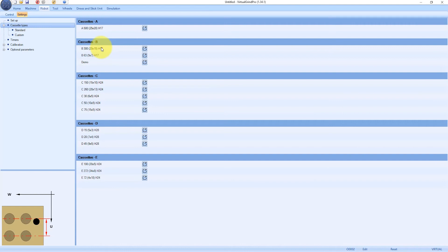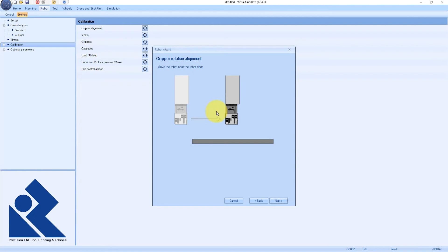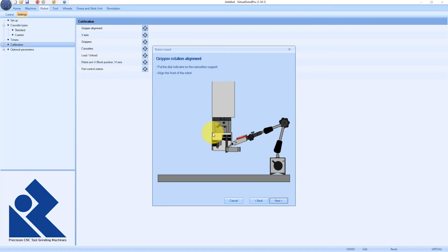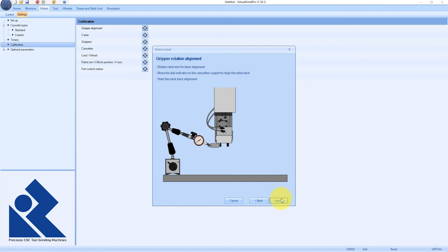For the calibration we have the different objects that need to be calibrated. When I click on the target here, a wizard opens each time, explaining what needs to be done. Here we're in the wizard for the gripper rotation alignment. We see summarized which cassette and which gripper type we have. When I press next, we see what needs to be done, explicitly written down, and each time we press next we follow the steps.